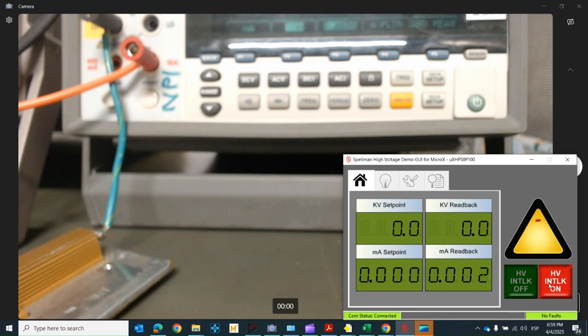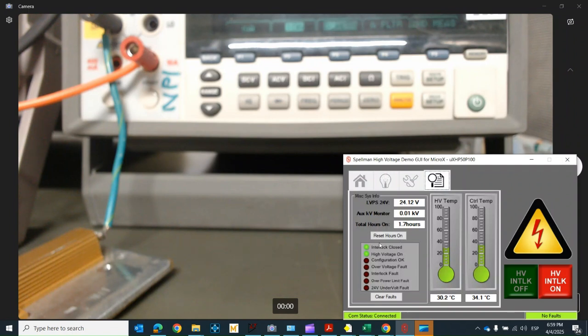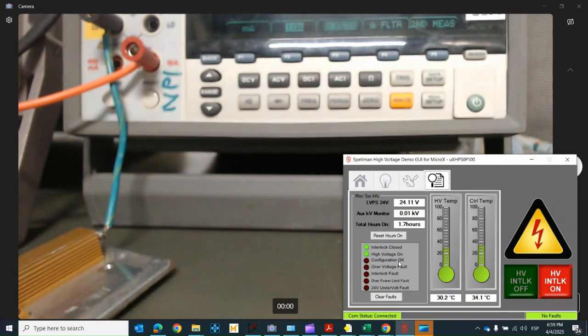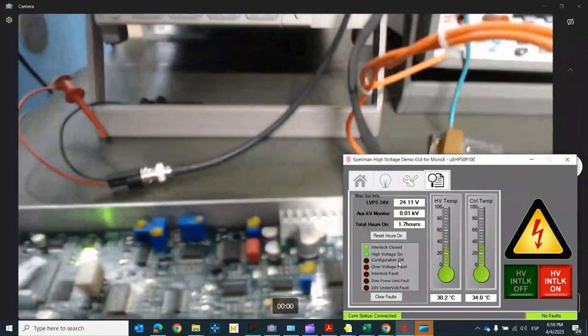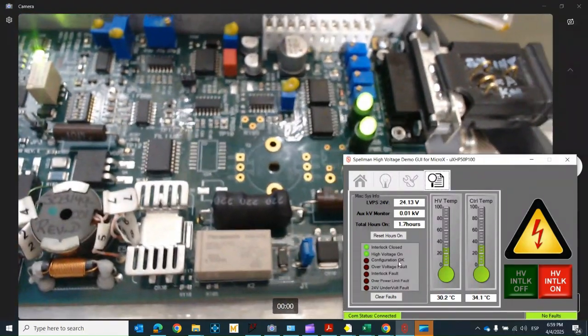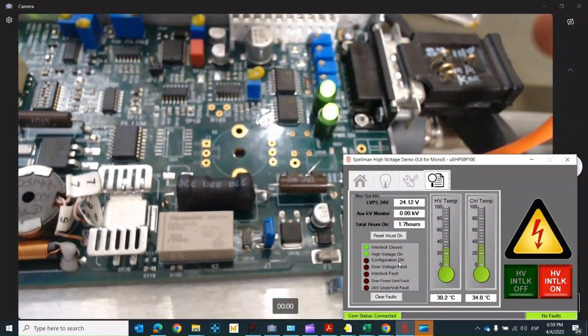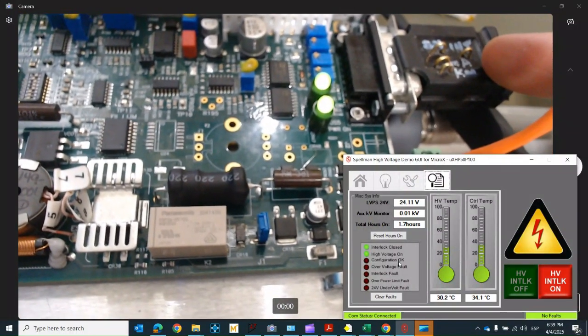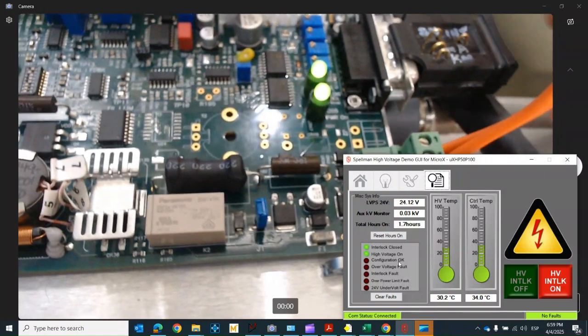We will now perform the interlock fault test. We will close the interlock after clearing the faults. Then, with the unit operating, we will proceed to remove the interlock connector from the 15-pin connector. High voltage on LED should turn off and power on LED should be blinking. The GUI will also issue an interlock fault and will also indicate open interlock.